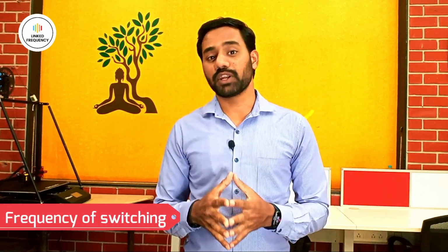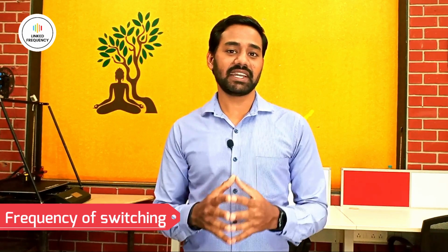Seventh one is the frequency of switching. When you are selecting an SSR, make sure that the SSR is capable of the frequency of switching at which you are expecting it to be used. If in case you are using an SSR for a small scale of switching or maybe a permanent switching from one state to another state with not frequent switching, then it is not a matter of concern. But if you are using it for a very high speed application or high switching application, then make sure your SSR is capable of operating at that particular frequency at which you are expecting it to be switched.